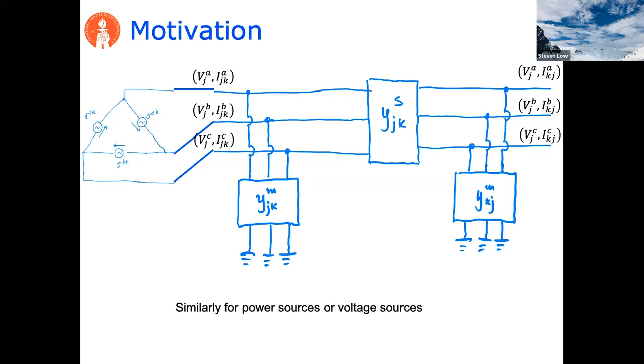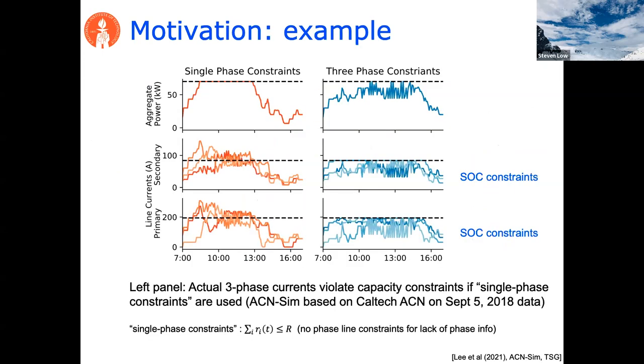Okay, 4 more minutes. Whether your three phase device is a current source, which may model an EV charger, or it's a constant power source or impedance and so on, it's the same story. There are internal variables which may be the only thing you can control. They will induce terminal variables which are observed externally and which interact over the network. So the connection between internal variables and terminal variables is really the key if you have to look at an unbalanced three-phase system. That's the issue.